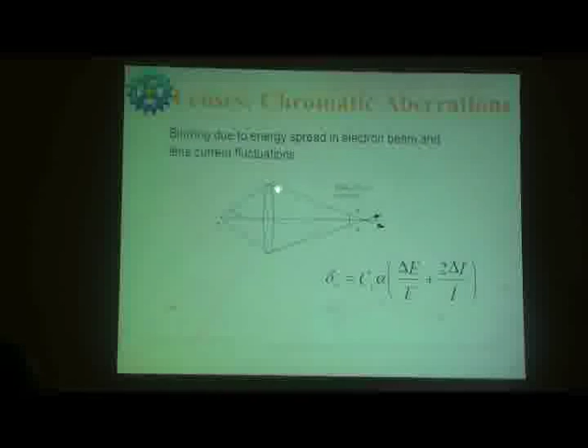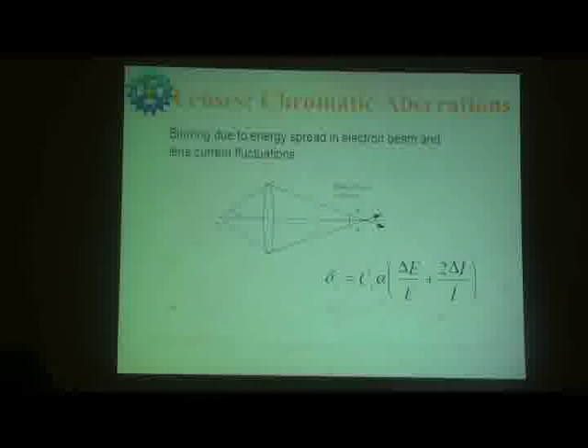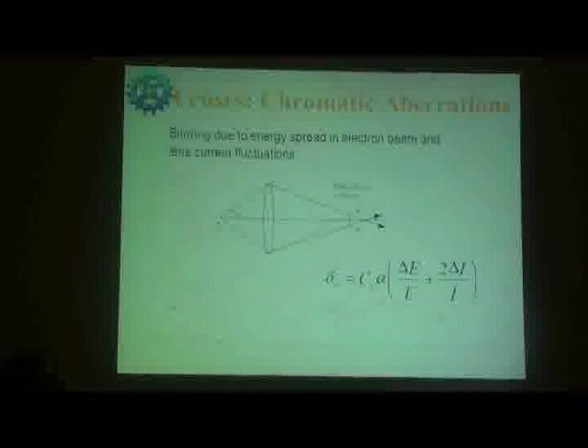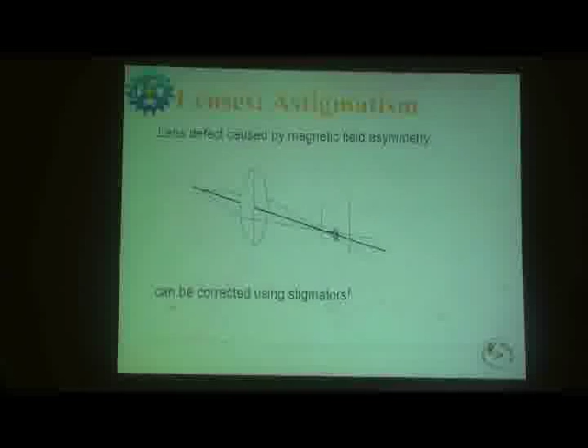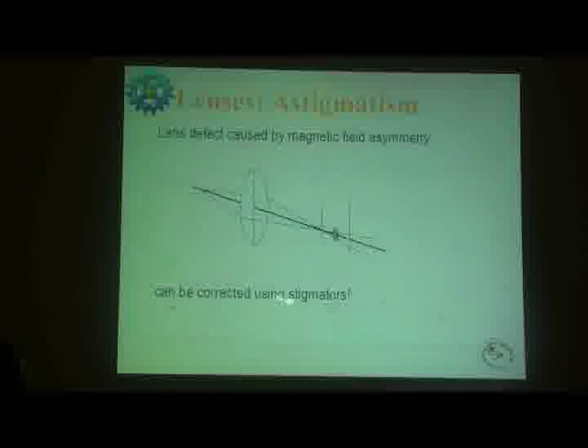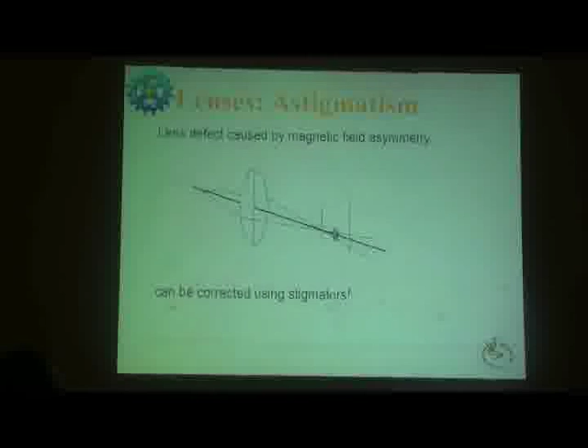All the electrons may not have the same energy coming from the same place. Sometimes high energy electrons will have a shorter focal length and low energy electrons a longer focal length. Then you have the chromatic aberration, just like what you see in a lens microscope. Then you have astigmatism. The electromagnetic lens may not be as symmetric as we expect. The asymmetry can give a diffused image, which will be asymmetric in the image formation. This can also be controlled by the stigmatic coils.